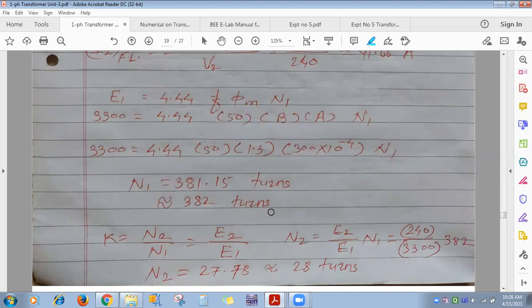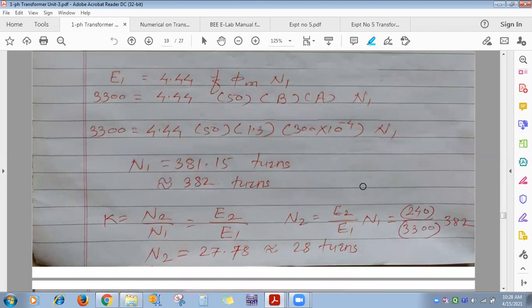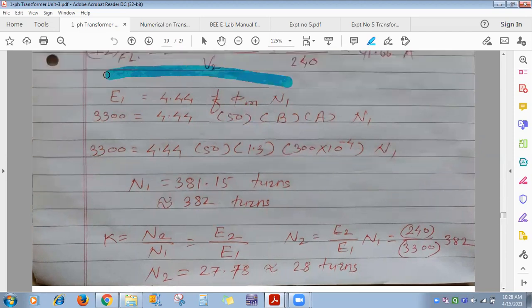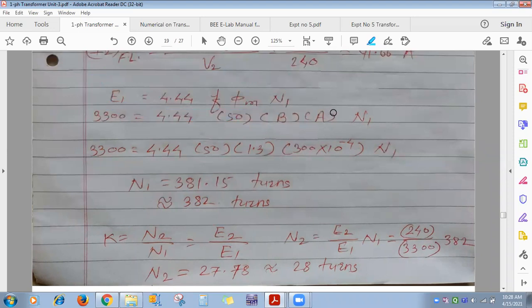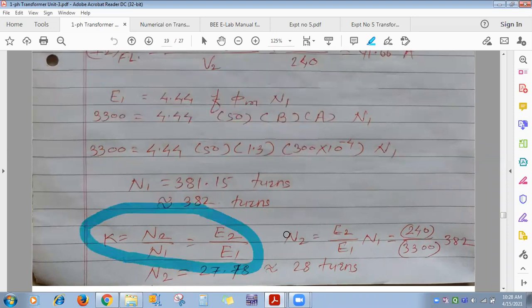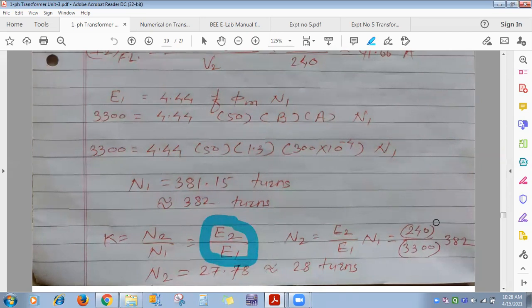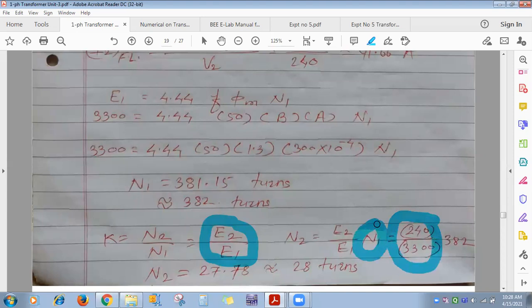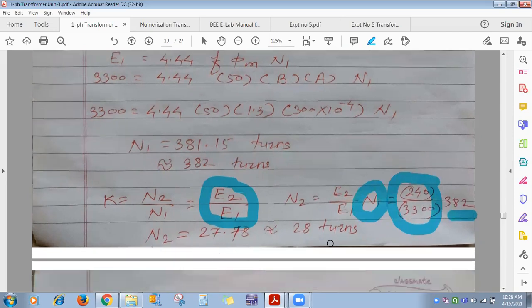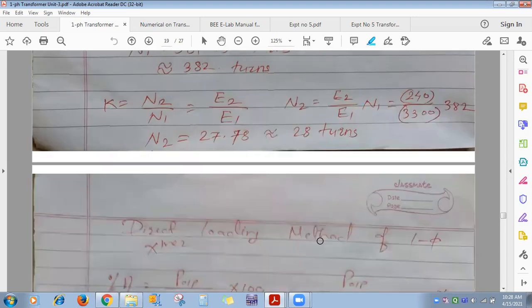For N2, use E2 = 4.44·f·Φm·N2, or use the transformation ratio: K = N2/N1 = V2/V1 = 240/3300. With N1 = 382, we get N2 = 27.78 ≈ 28 turns.